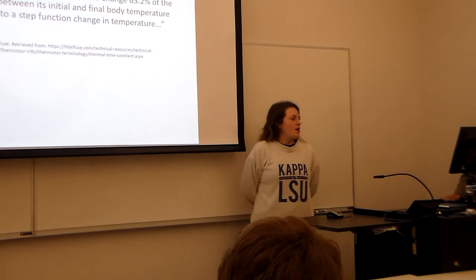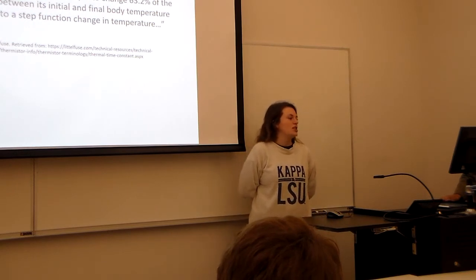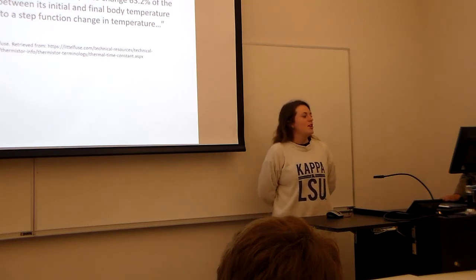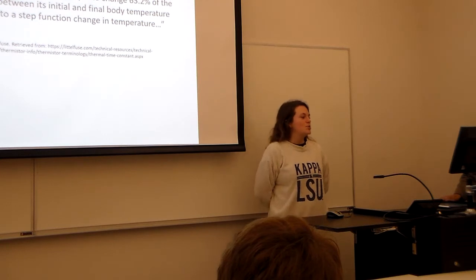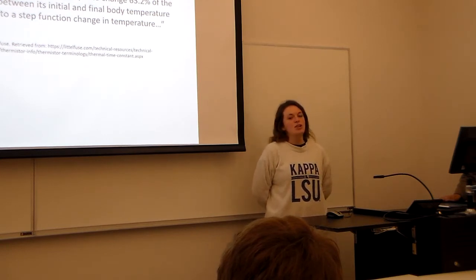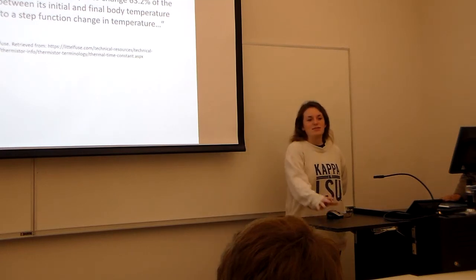So littelfuse.com describes a time constant as the time required for a thermocouple to change 63.2% of the total difference between its initial and final body temperature when subjected to a step function change in temperature. So it's essentially more of a normalized version of the time it takes to change temperature.